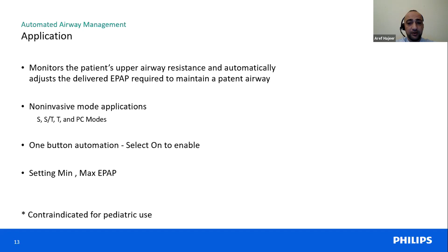So it's a feature, and once you activate it, it will give you the facility to add EPAP minimum and EPAP maximum for the patient. Then the device will start with the minimum EPAP. Whenever the device feels that there is an airway obstruction, it starts to increase the EPAP automatically without any manual adjustments. For the setting, you only set minimum and maximum EPAP, as I mentioned. It's one button to do the automation, and it's contraindicated for pediatric use. This is according to what we tested the device with.